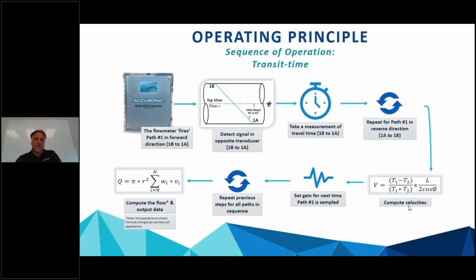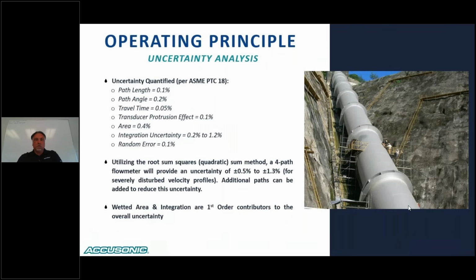We have the path angle, and that is the path angle there with respect to the center line of the pipe, typically 45 or 65 degrees. And the travel times that we've measured. Those all compute into velocities. We do this over and over again until ultimately on the bottom left side, we come up with our flow rate calculation. And all it is the wetted area times the weighted average of the individual velocities.